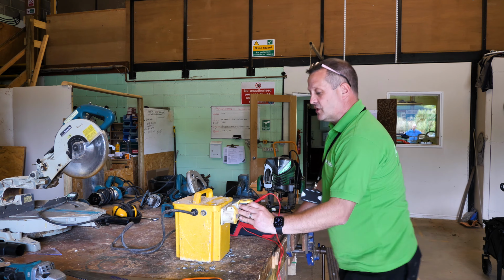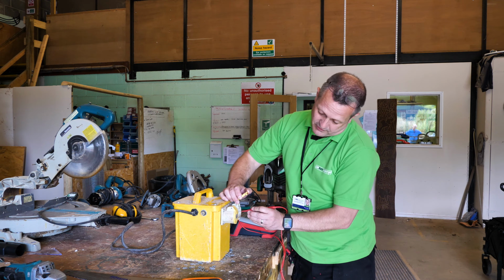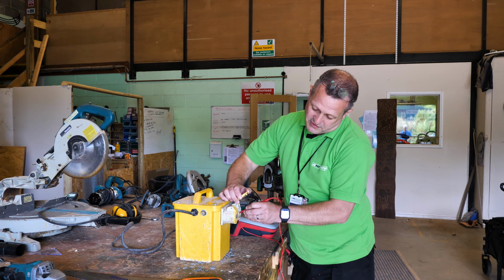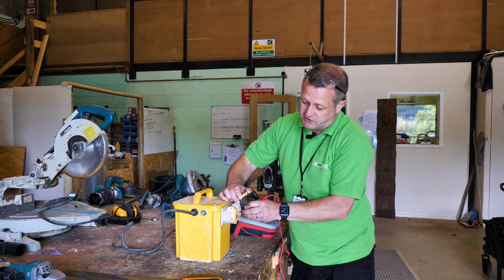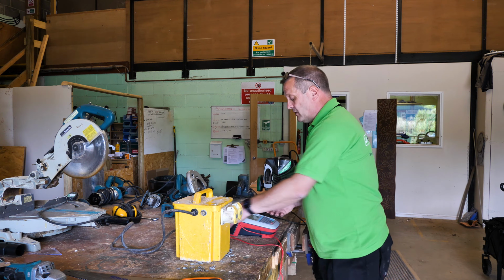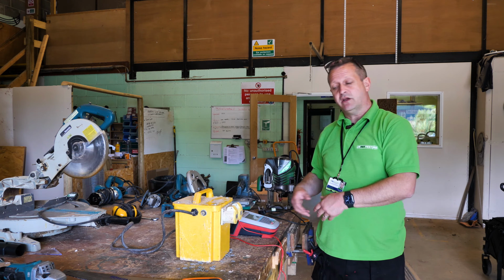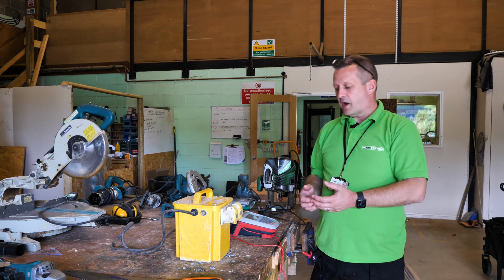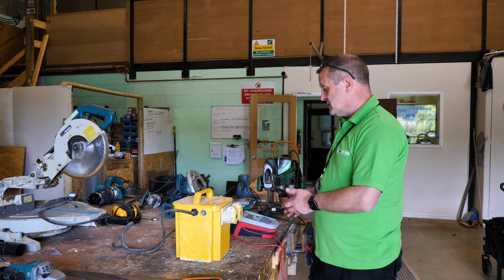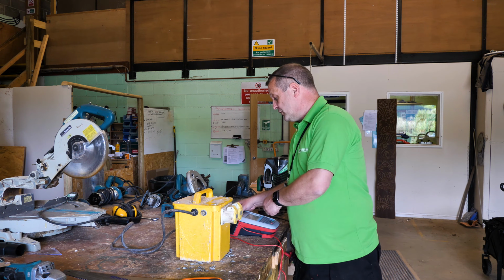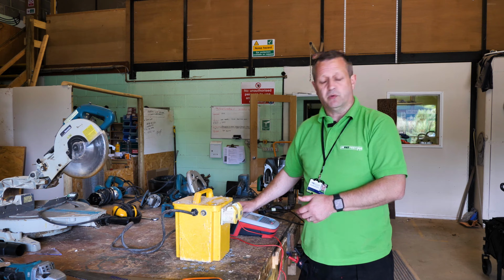And that is the transformer complete. So the knack on that one is just to slide the probe along the inside until you can feel the copper sheath inside for the earth. Again, we then record the results onto the machine or onto your laptop or your iPad or paper if you still use that, and then we would mark that up accordingly and attach a new fresh label.